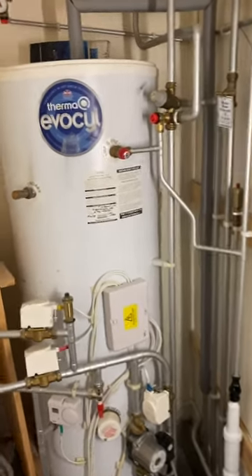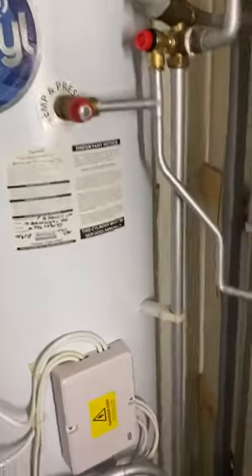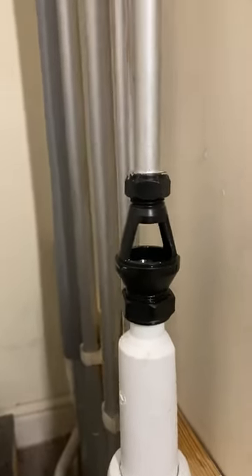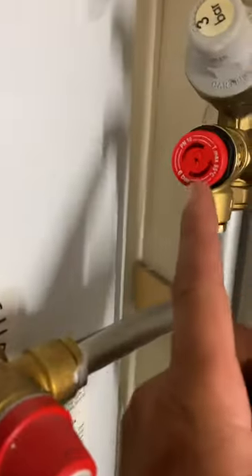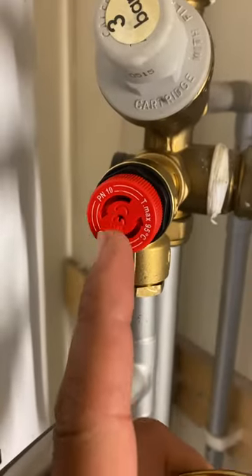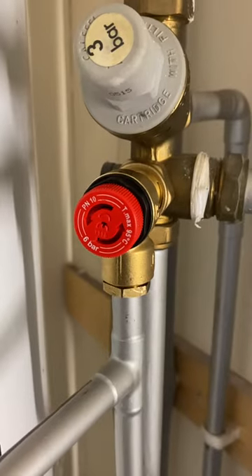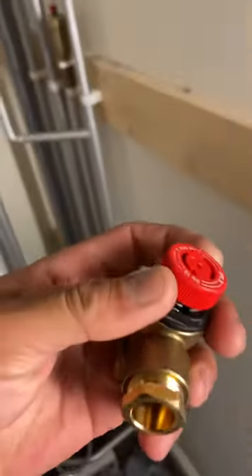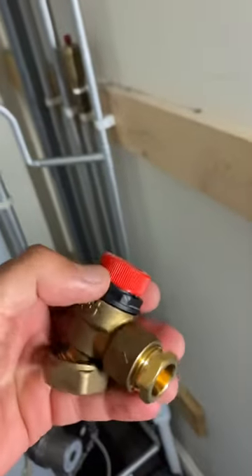We had a leak and overflow pipe before, and found out the problem was from this pressure valve, which is 3 bar, PN 10 temperature, maximum 95. So I opened the valve inside.